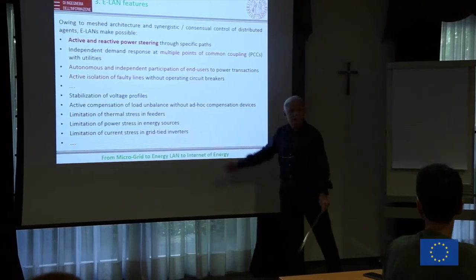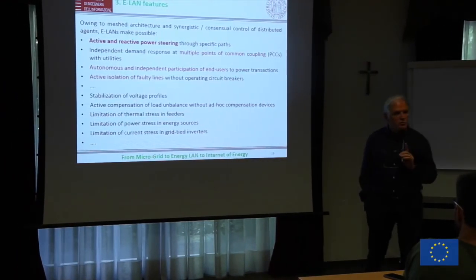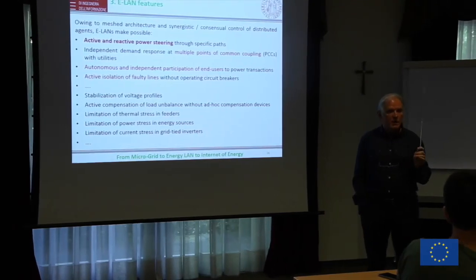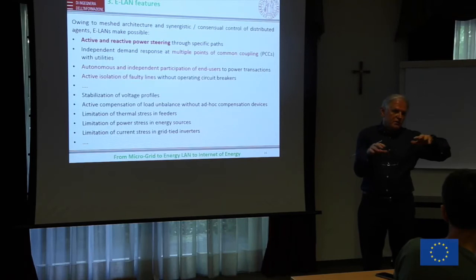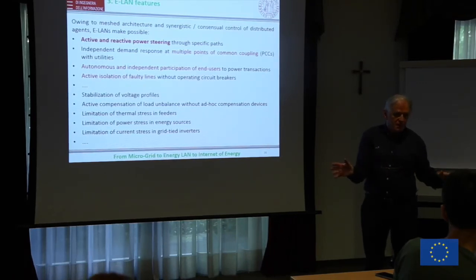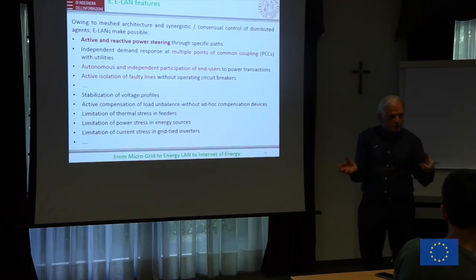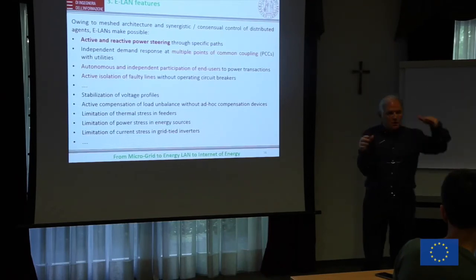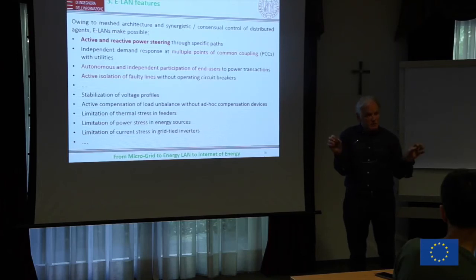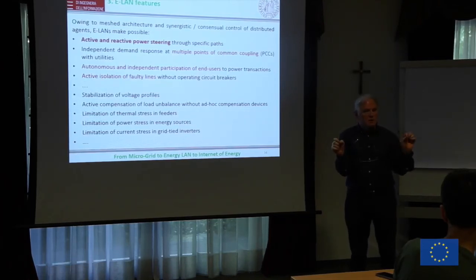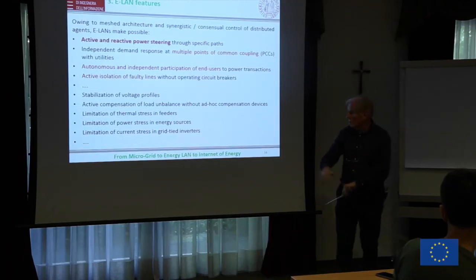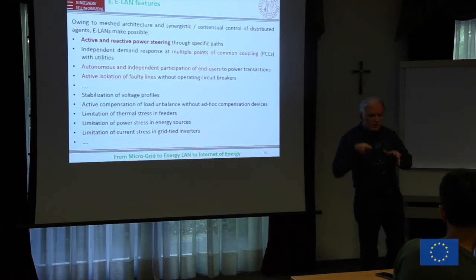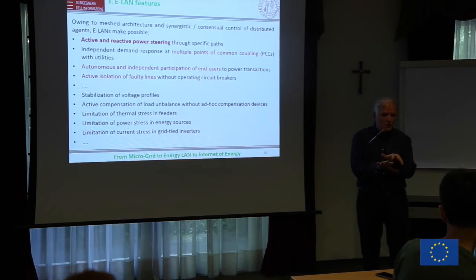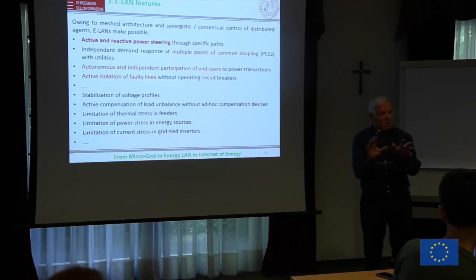We are putting together a number of objectives that are not usual in power flow analysis. Power flow analysis normally is not applied in low voltage systems, which are too distributed, too complex to deserve analysis with power flow systems. Normally, power flow analysis is made for medium voltage, high voltage systems. In that case, you act on specific nodes in the grid in order to divert the power from one part to the other. Here, you can do this locally at a very low level and in a very punctual situation.